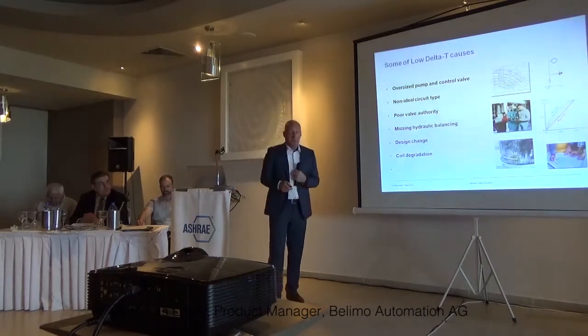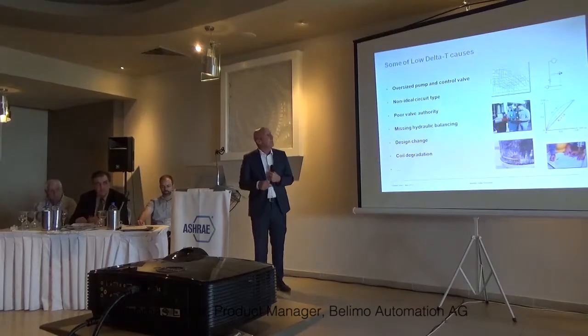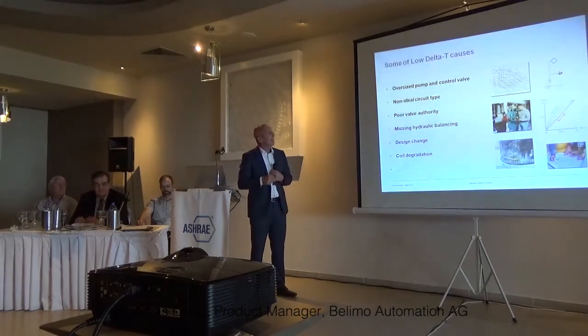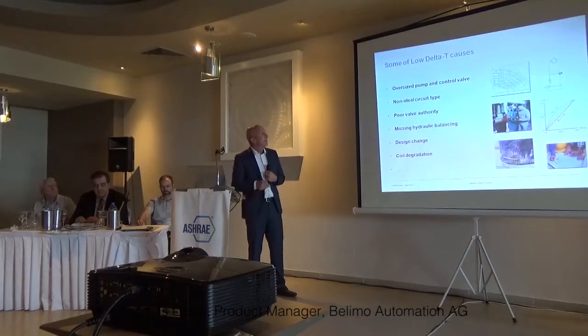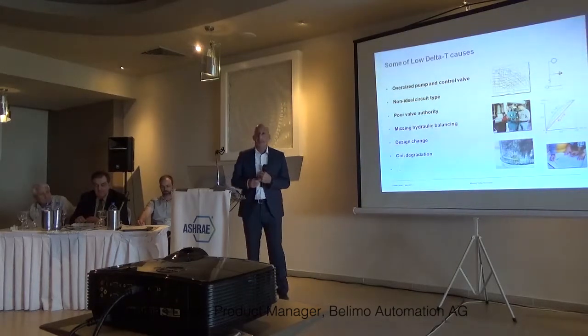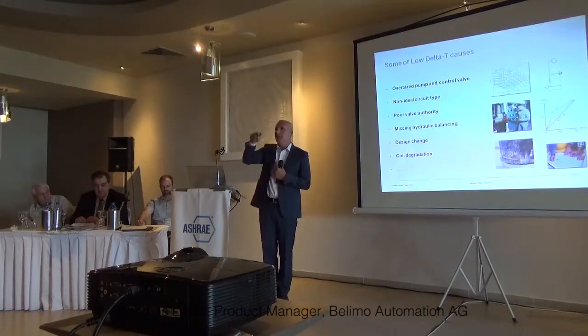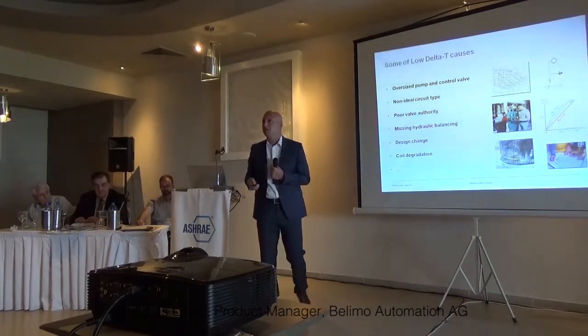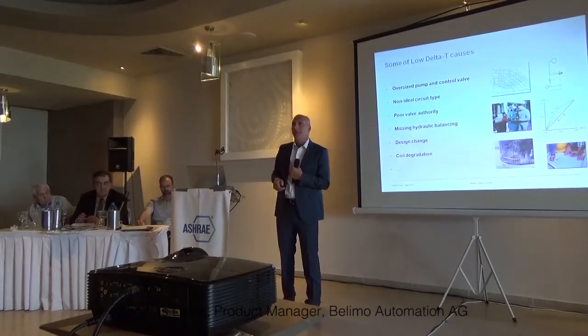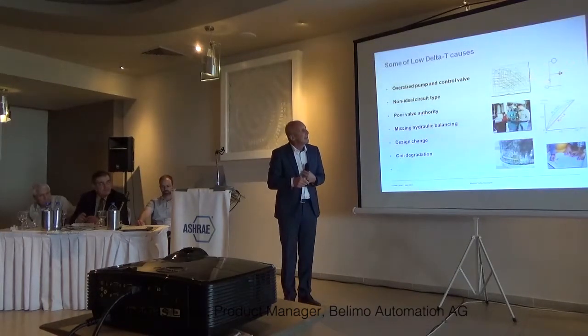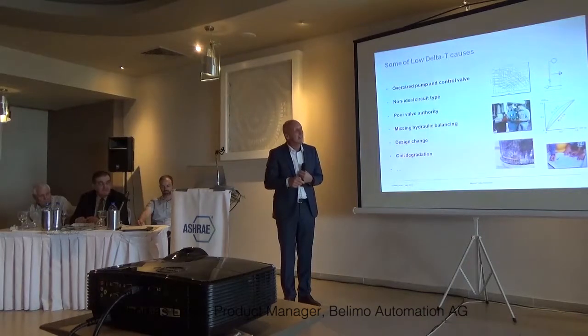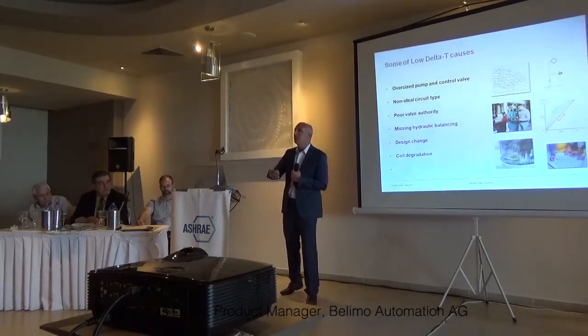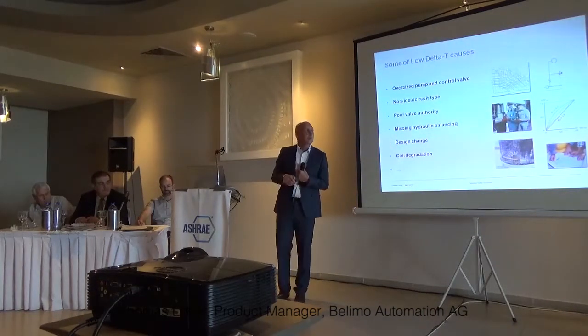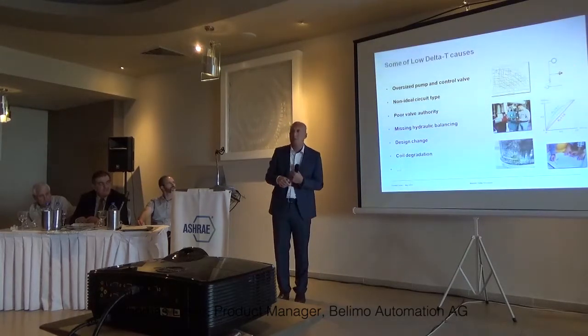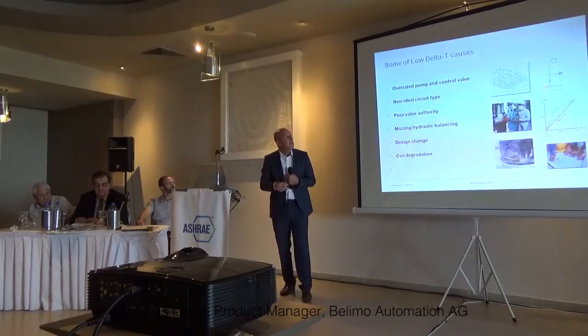The causes of this low delta T, again and again: a too big pump, and not ideal circuit type. I don't know what kind of hydraulic circuits are preferred here in Cyprus, but in terms of energy efficiency, I would recommend to think twice if you want to continue to use these diverting circuits. The reason is a quite simple one.